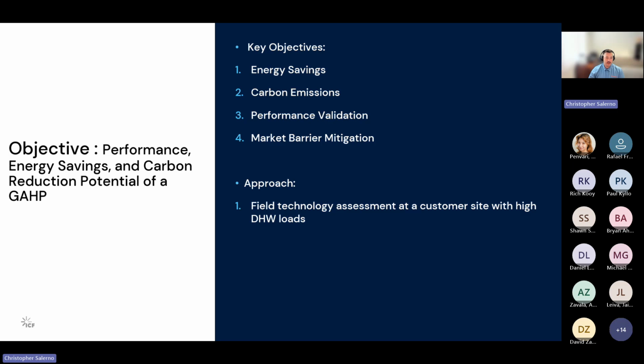So next we go over to the objectives. So the key objectives of this was obviously characterizing energy savings from reduced gas consumption by installing a more efficient water heating system or retrofitting to make it more efficient. And so the second objective was initially to characterize the carbon emissions reduction from using less gas to meet the same level of service for the domestic hot water needs. And the third was performance validation. We want to be able to validate these gas-fired absorption heat pumps in domestic hot water only applications and be able to support more of these applications.